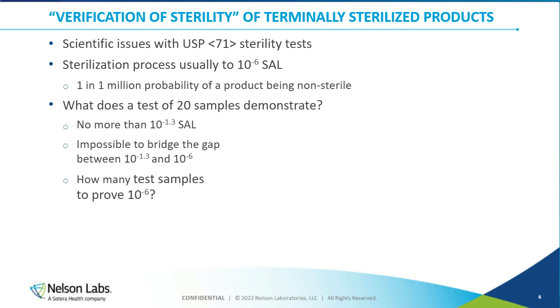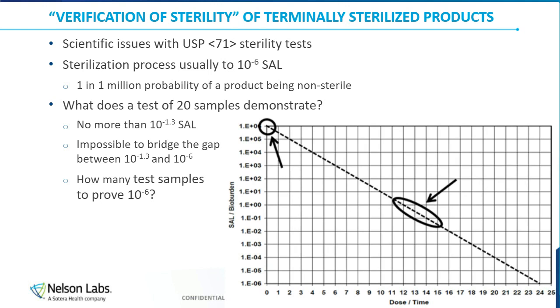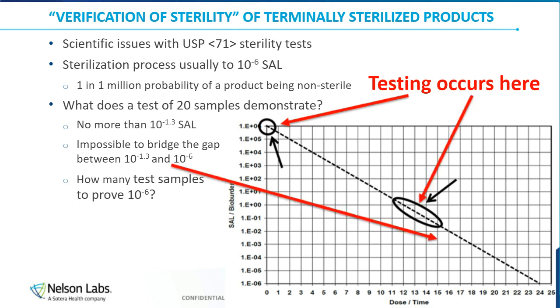So graphically, here's what this looks like. Let's say this is either product bioburden or the bioburden of a biological indicator at 10 to the 6, like 1 million CFU. And those of you that are familiar with microbiology and sterilization know that roughly we have a straight line. And so we're usually testing here at the beginning, where we understand what the initial contamination or bioburden count is. And then we're testing somewhere here in the middle, when we're actually testing for sterility. And the problem you see here, just to show it graphically, is you have all that dashed line below where testing is actually occurring, extrapolating to 10 to the minus 6, 1 in a million. So there's that big gap between where you've tested and where you're trying to prove. And there's just no way to do that scientifically.